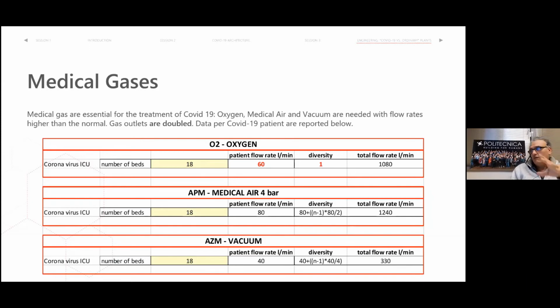You cannot, for oxygen in this department, apply a diversity other than 100. You must have 100% of activation of all these outlets. So the total flow rate for 18 patients is quite huge. This has to be taken very much into account when you design this, because generally in a normal ward, you have 10 liters per minute per patient, not 60. But this is very important because they use some devices for the people, respirators or whatever, that sometimes need a lot of oxygen.